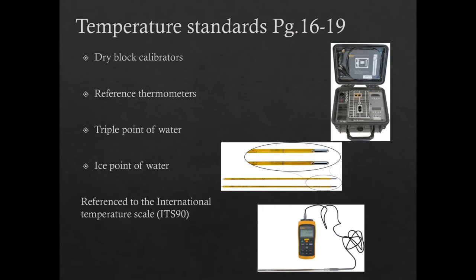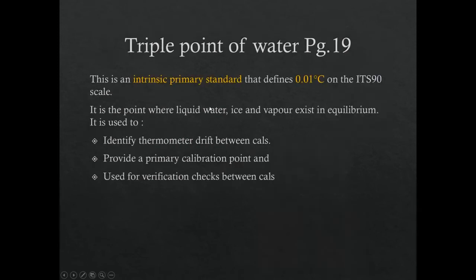Some temperature standards are intrinsic standards: the triple point of water and the ice point of water are examples. Their values are tied to physical or scientific properties — we know ice melts at zero degrees, so a well-stirred container of ice water is right around zero. These temperature devices are referenced to the International Temperature Scale (ITS-90). The triple point of water is an intrinsic primary standard, and it defines 0.01 degrees Celsius on its scale.